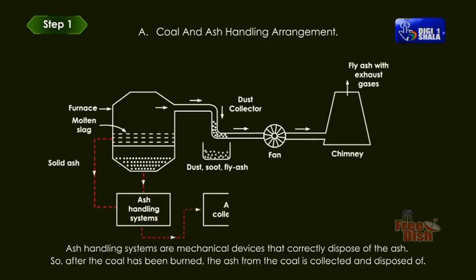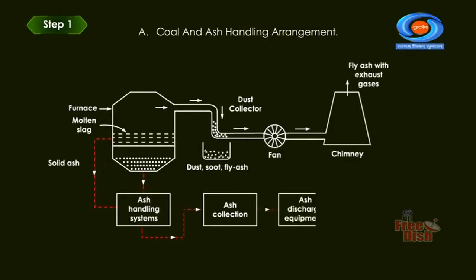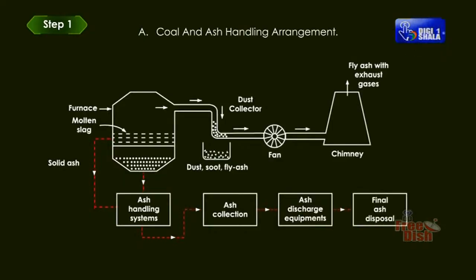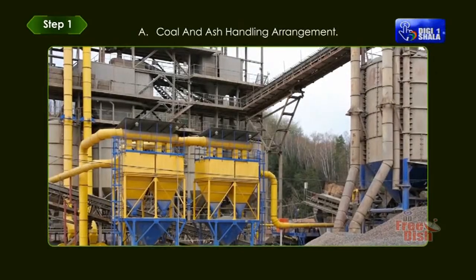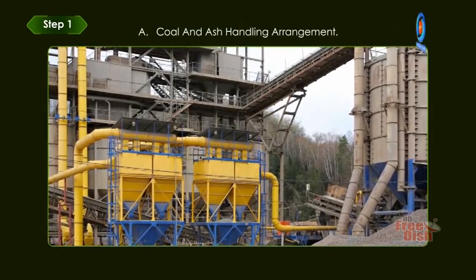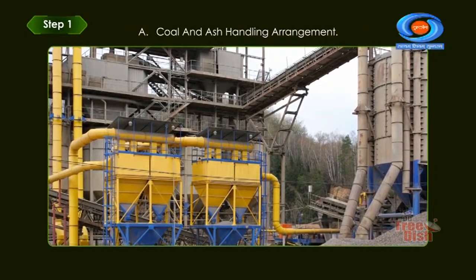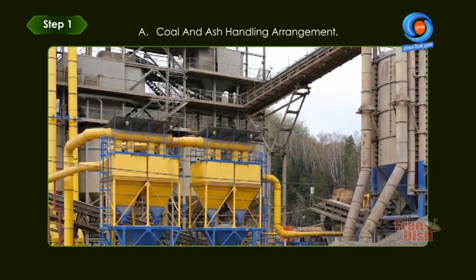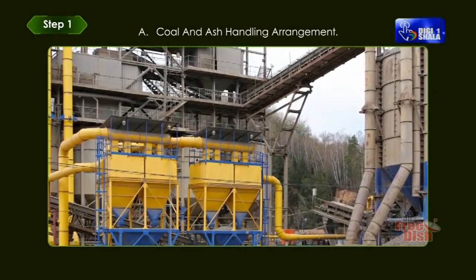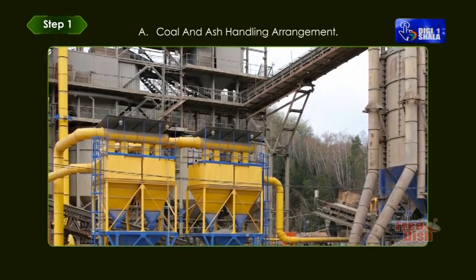So after the coal has been burnt, the ash from the coal is collected and disposed of. Before disposing of it, it must be cooled down to a manageable temperature. It is then transferred to a disposal or storage area and used in various industries such as cement plants, construction and other similar places. The residual product, which may contain ashes or gases, will be collected by an electrostatic precipitator, that is ESP, and stored in the hoppers at the bottom of the ESP.